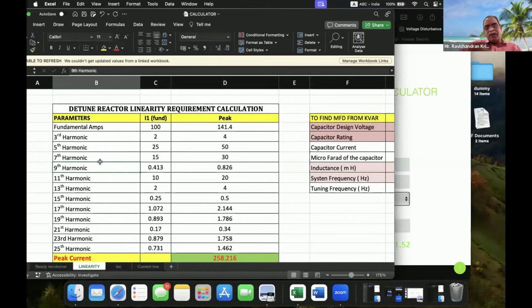First is the resonance frequency—we have to understand this whether or not we're connecting the load; that's not the issue. Just by having the system resonance frequency, it's naturally created within the design, along with the transformer, the capacitor, and the available short circuit level at the LV point. These 3 parameters are enough to calculate the system resonance frequency.